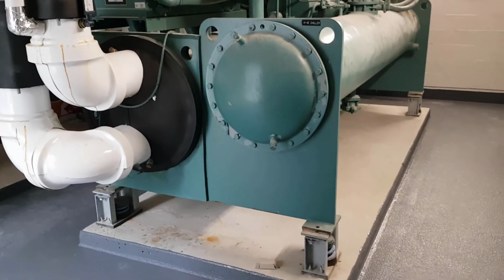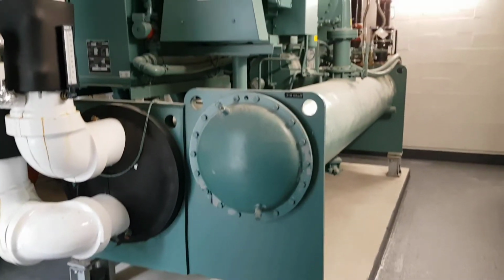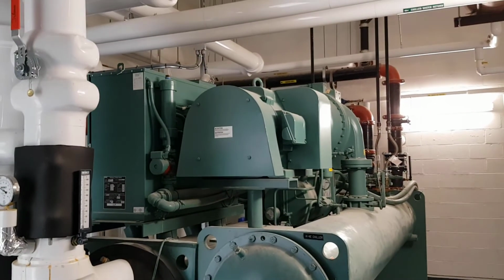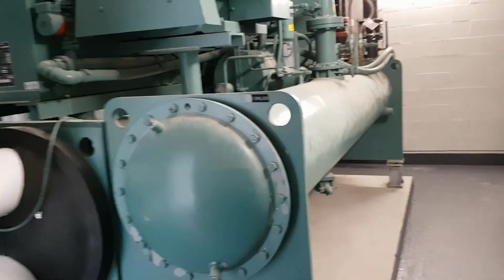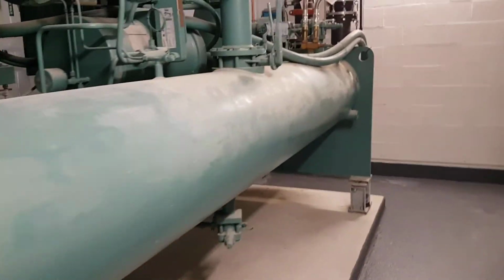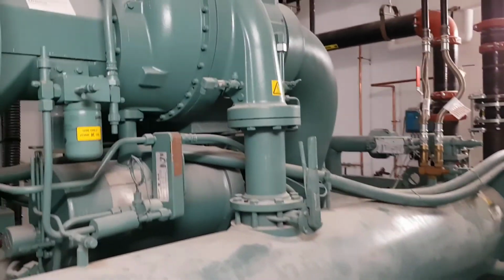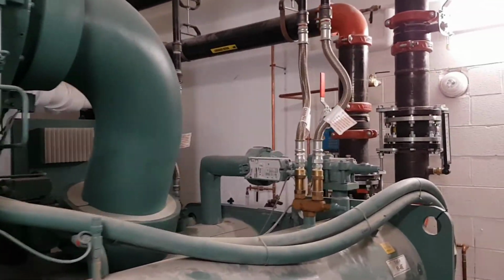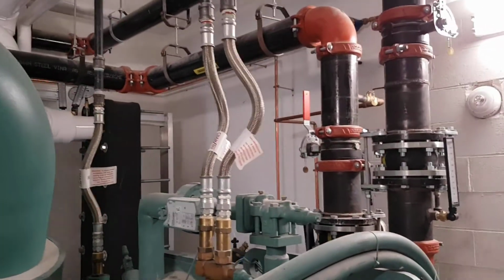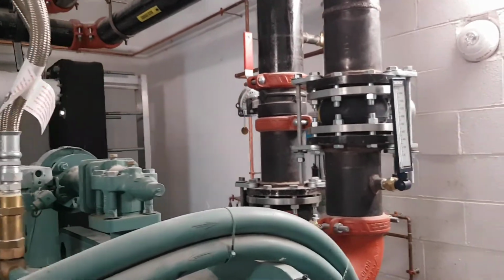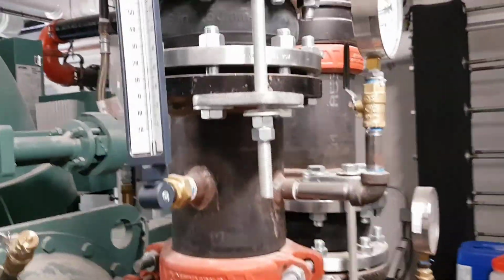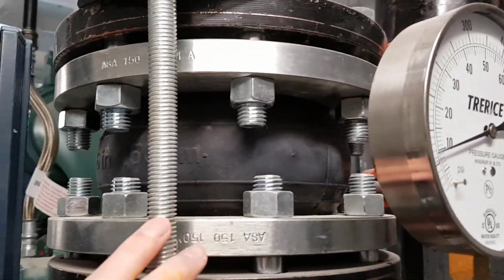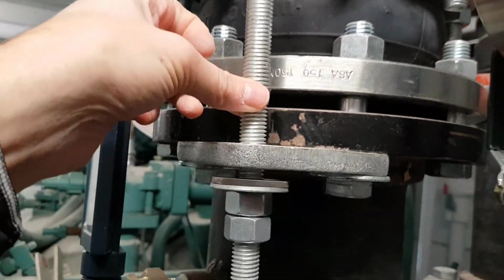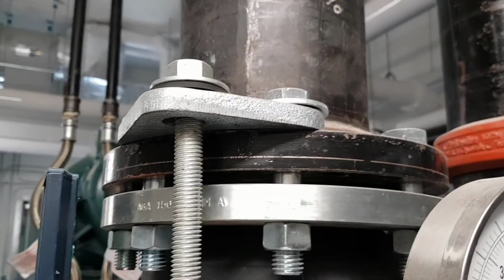Starting on the far side of the chiller, we'll walk past the condenser shell and note that the chiller is mounted on springs and any pipes attached have some kind of flexible component to limit the transmission of vibration to the structure. As typical, the condenser water pipes are not insulated, allowing us the opportunity to see the single-sphere neoprene expansion joint flexible connectors complete with control rods. Here, I'm confirming that the rods are loose, which is important to minimize vibration transmission.